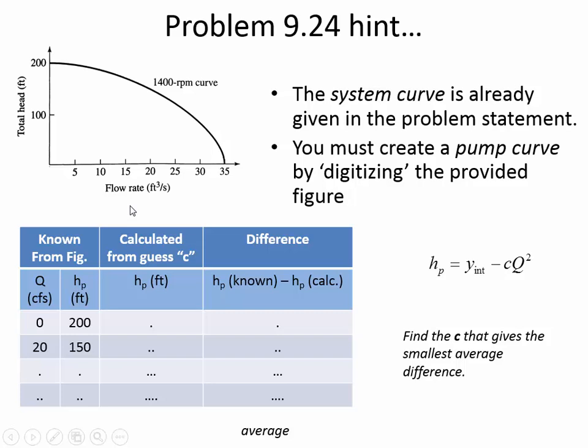So what that means is, go through here and identify when the Q is 0, what is the HP? When the Q is 20, what is the HP? And so on. You could also do, for HP of 100, what is the flow rate? For 50, what is the flow rate? And so on. So that's known from the figure. And then what you need to do is have some guess C value somewhere else, like a cell at the top, and then use this equation to get a predicted H sub P based on the guess value of C. Then you look at the difference between the known and the guess value of the H sub P's, and you want to minimize the average difference between the known and the guess value.